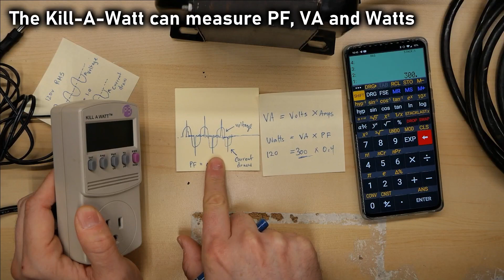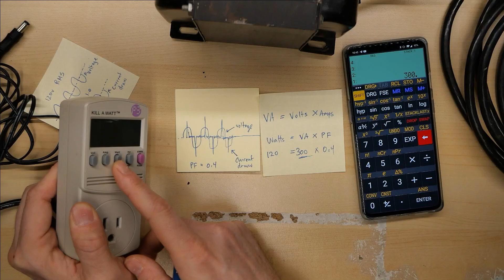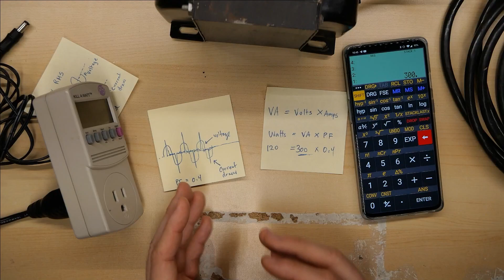If we plug this theoretical power supply into here, we could switch to PF power factor and measure it, but we could also press the VA button and read the VA directly, which would help avoid doing a little math. The problem is the power factor might be 0.4 most of the time just because of how the power supply works, but unless you load that power supply up as hard as you can, it'll be hard to get an accurate VA rating.